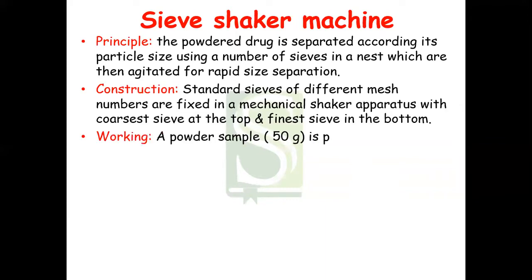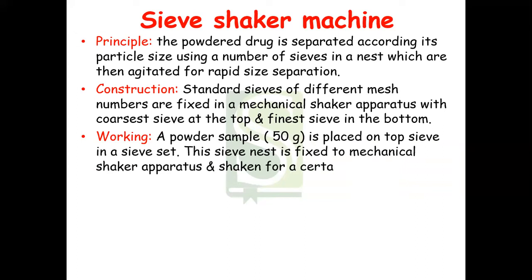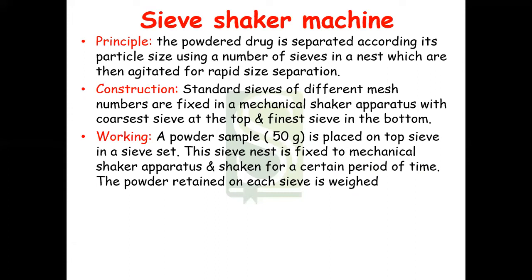The equipment used for the sieving method is the sieve shaker. This machine works on the principle that the powdered drug is separated according to its particle size using a number of sieves in a nest, which are then agitated for rapid size separation. The construction is simple — it has standard sieves of different mesh numbers fixed in a mechanical shaker apparatus with the coarsest sieve at the top and the finest sieve at the bottom. You place 50 grams of powder on the topmost coarsest sieve, fix the nest, and shake it for 10 to 15 minutes.